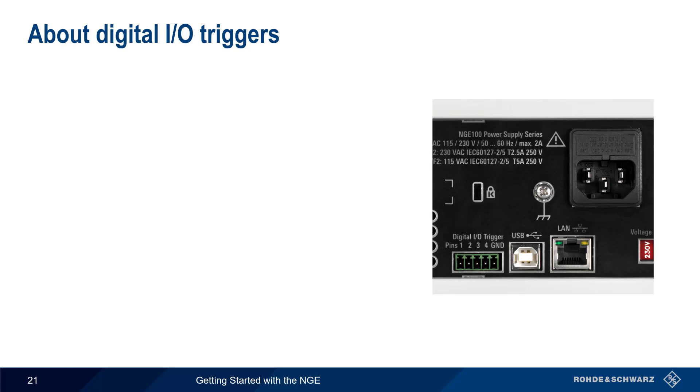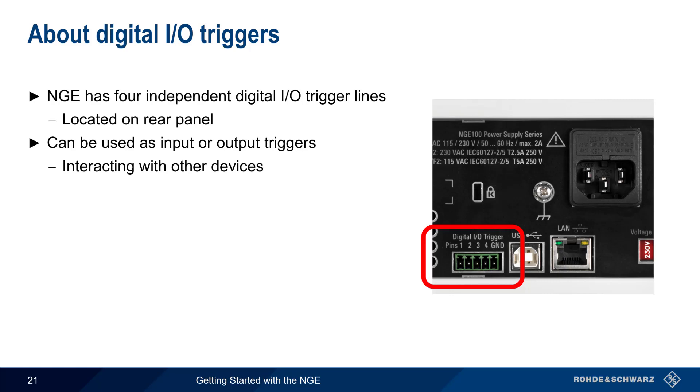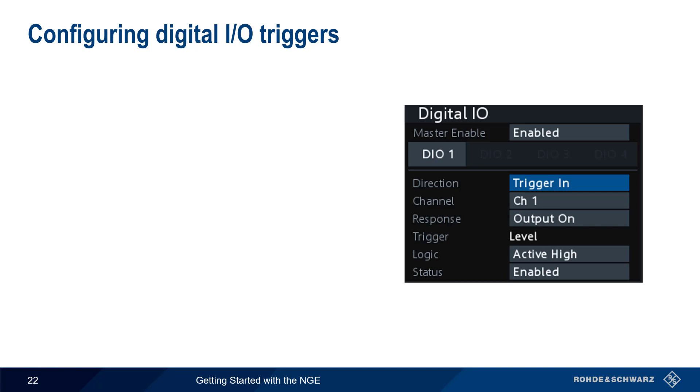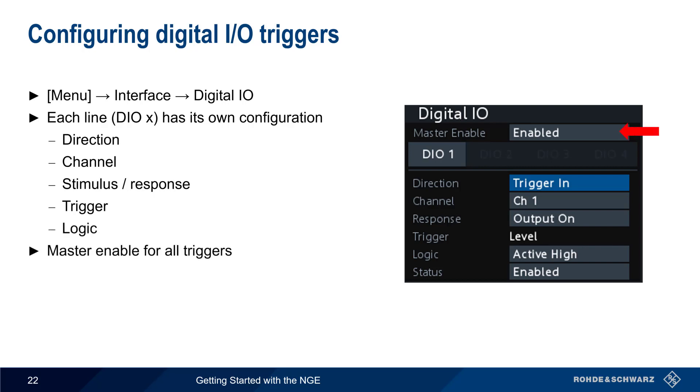Another useful feature is digital input and output triggers. The NGE has four independent trigger lines located on the rear panel. Each of these lines can be used as an input or output trigger, making it easy to integrate the NGE with other devices. For example, an external event could be used to turn the NGE output on or off, or the NGE could inform another device when a protection threshold is crossed. There are a wide variety of trigger conditions or actions, including turning the output on or off, having the voltage or current exceed a user-defined threshold, crossing a protection threshold, or running an EasyArb sequence. To configure the digital I/O triggers, press the menu hard key and then Interface Digital I/O. Each of the four lines has its own configuration for direction, channel, stimulus or response, associated values, and logic state. There is a master enable for all triggers, but each trigger can also be enabled individually.